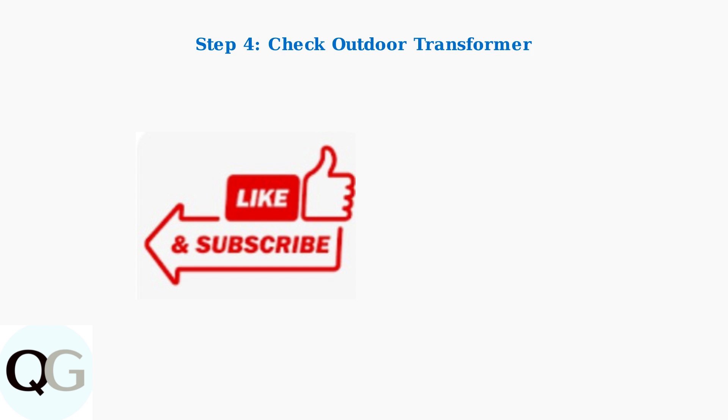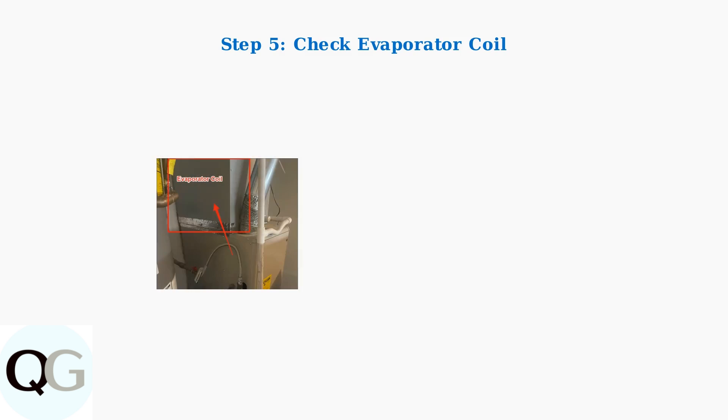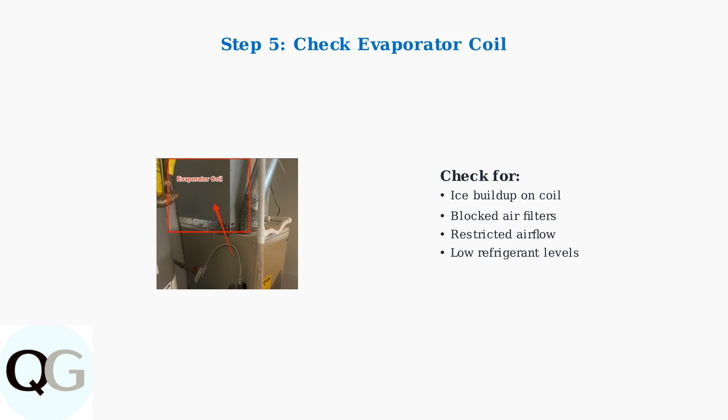Examine the outdoor transformer for any visible issues. The transformer provides the low voltage power needed for thermostat communication. If you suspect a frozen evaporator coil, check for airflow restrictions and low refrigerant levels. A frozen coil can trigger error code 126 as a safety lockout.